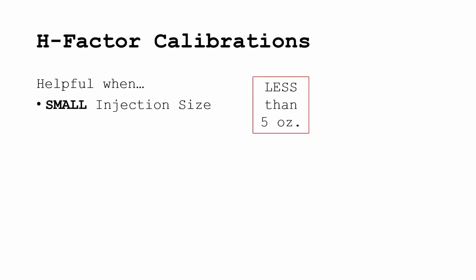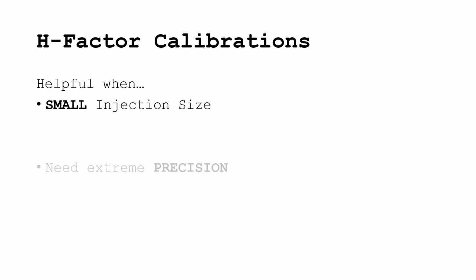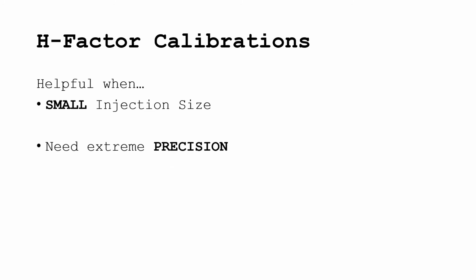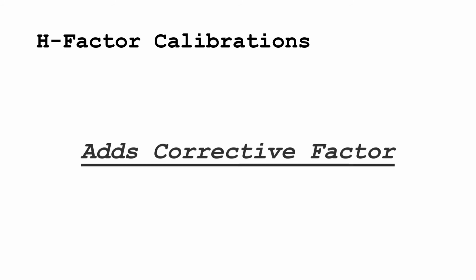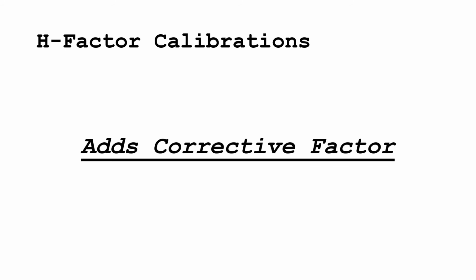While all systems can do an H-factor calibration, not all chemical injections need an H-factor calibration, but it is helpful in certain situations, like when the injection size is small, less than 5 ounces, or there is a need for extreme precision. The H-factor calibration does not change the calibration but adds a small corrective factor to the injection in order to increase its accuracy.